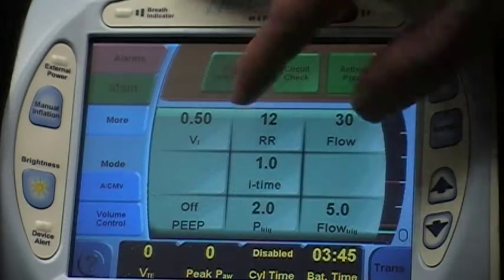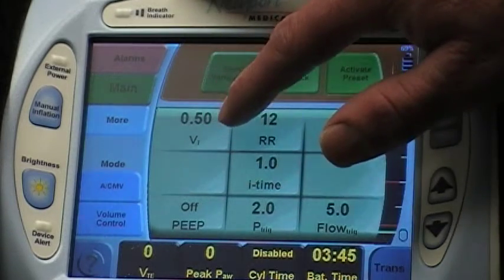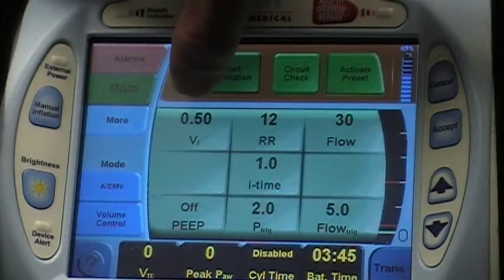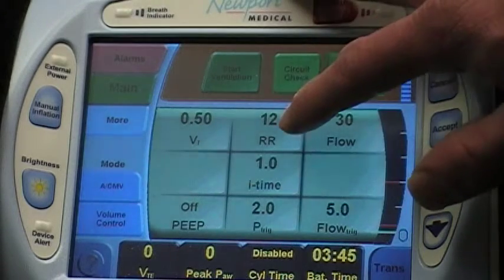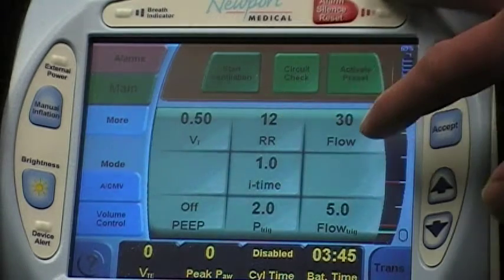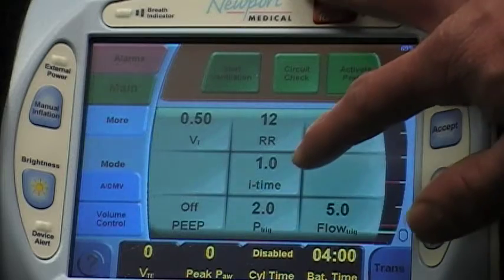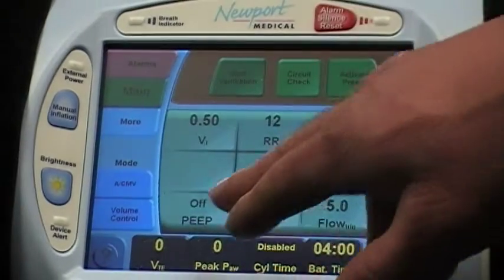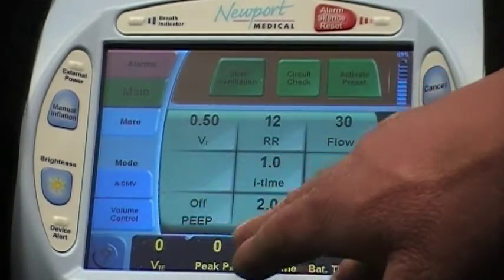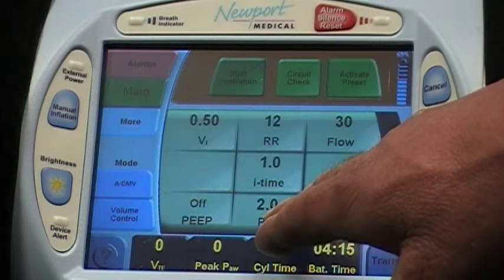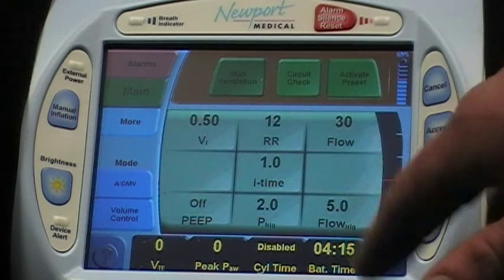I'm going to go back to my main screen here. As you can see, I've got a tidal volume of 500 on this vent. It reads 0.50. We've got a respiratory rate of 12, a flow of 30, inspiratory time of 1. I do not have any PEEP turned on, and my P-trig's at 2.0, with a flow trig of 5.0.